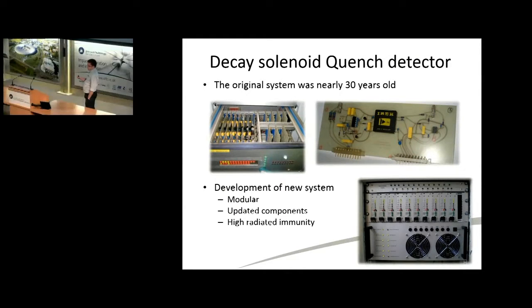Quenches are basically, for those that don't know, little warm spots within the superconducting material. When you're chucking 200-300 amps through it, they can quickly get very warm because obviously these strands are much thinner than your hair. So putting 300 amps through a warm spot there will quickly warm up the magnet. What can happen then is that very large voltages can be generated because the inductance is still the inductance, unfortunately, and you can really damage the magnet.